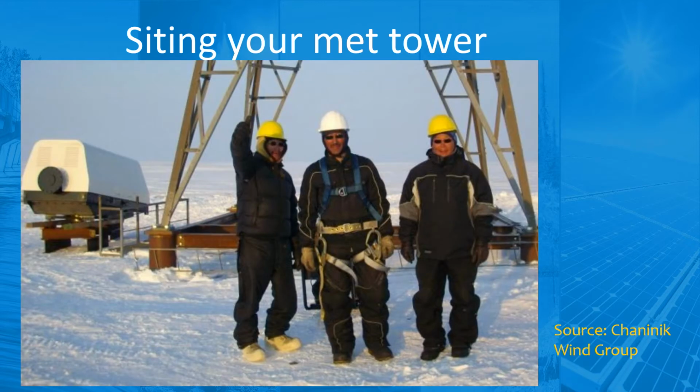One final consideration in MET tower and turbine siting involves a species very dear to our hearts, people. Turbines and MET towers pose an unlikely but potentially severe risk for failure or collapse. In some cold environments, ice throw is a risk. As the typical collapse zone safety perimeter is 1 1/2 times the height of a structure, it is recommended to site turbines and MET towers at least 3 times the height of the structure away from occupied buildings to allow for extra safety margin.